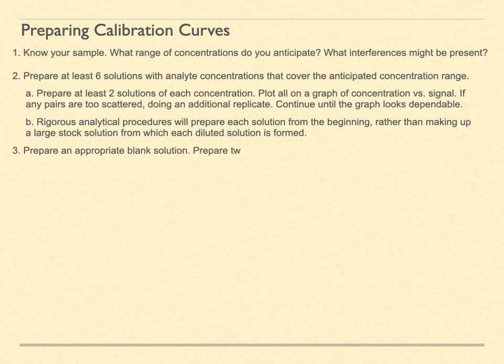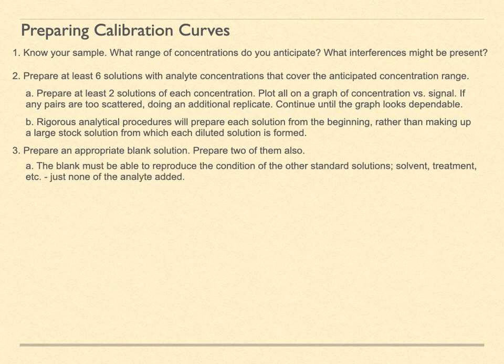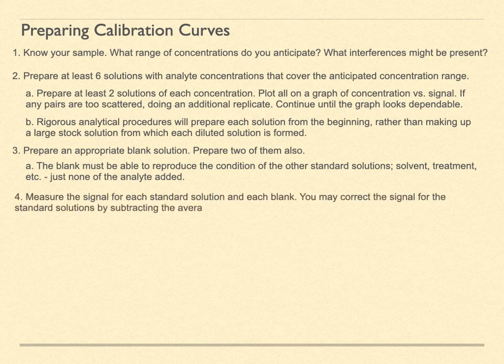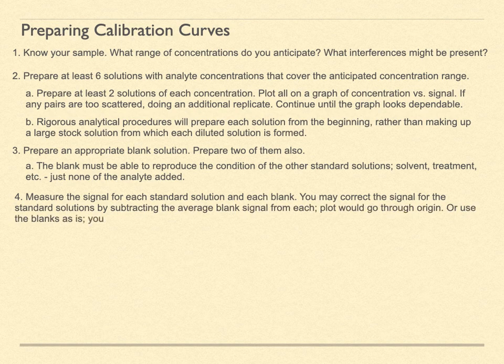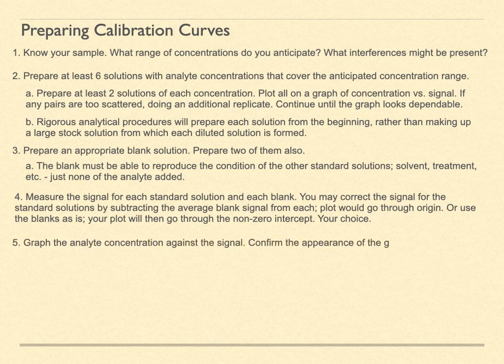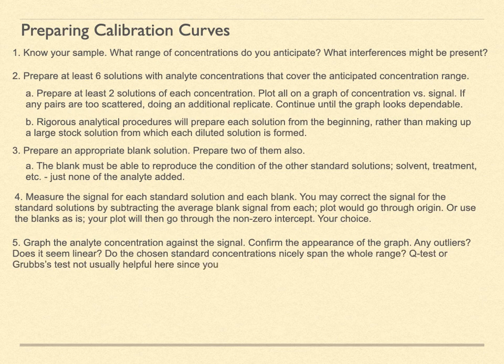Now prepare a blank solution. You should have a couple of them also. The blank needs to replicate the chemical conditions of the other standards. Everything except the analyte. Measure the signal for each standard and each blank. In the past, calibration curves were plotted by hand. The blank signal was subtracted from all the other data points. The resulting curve would pass through the origin. With computers, however, we can fit the curve and plot that with a non-zero intercept. You can do it either way. In any case, the blank data is incorporated as part of the calibration process.